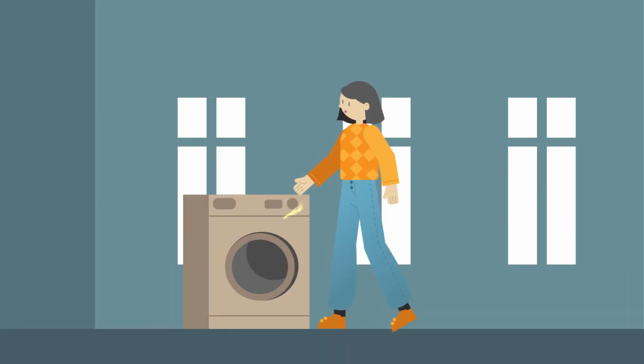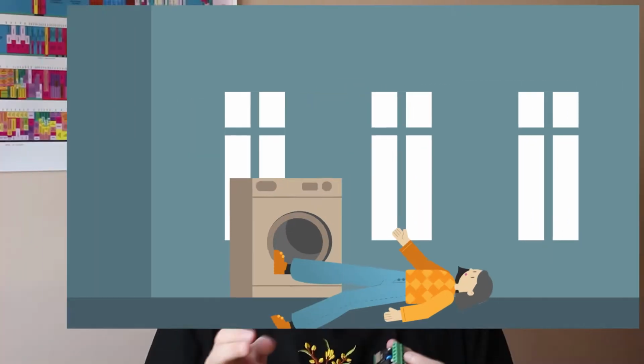That is a security feature within the house. For example, your washing machine has its line and neutral to make the motor turn, and the outer metal case is usually connected to earth. The main point is that if somebody touches the outer shell, you don't want that person to get electrocuted. So the way to do that is to connect the earth to the neutral.